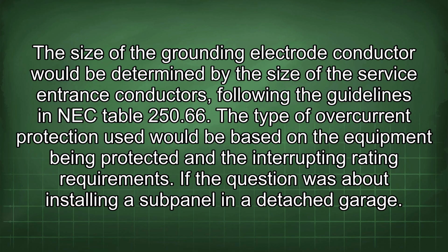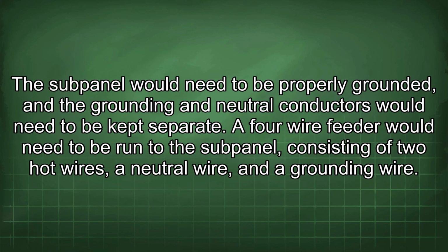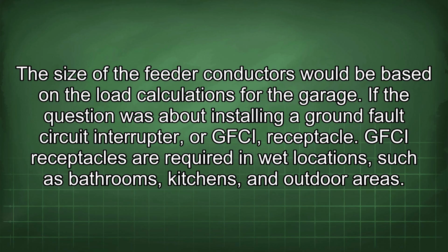If the question was about installing a subpanel in a detached garage, the subpanel would need to be properly grounded, and the grounding and neutral conductors would need to be kept separate. A 4-wire feeder would need to be run to the subpanel, consisting of 2 hot wires, a neutral wire, and a grounding wire. The size of the feeder conductors would be based on the load calculations for the garage.